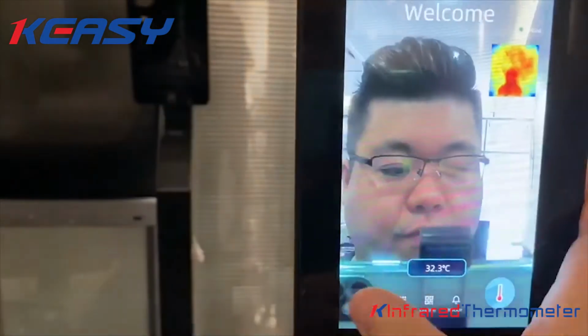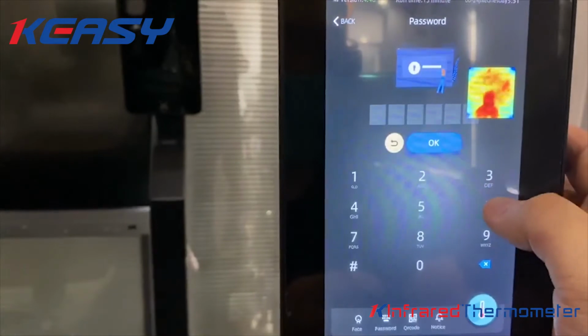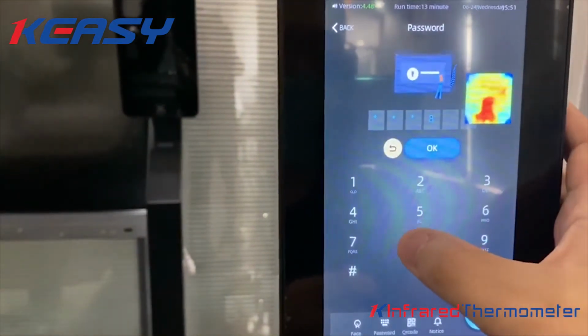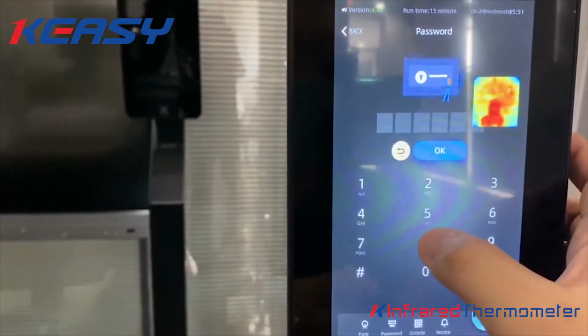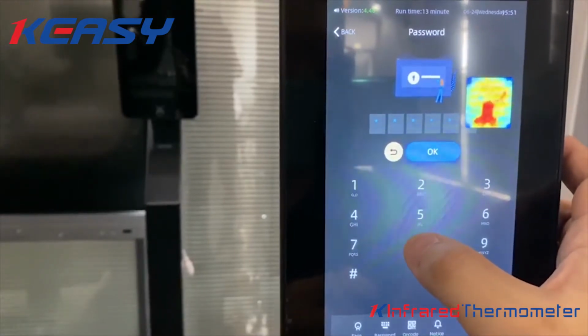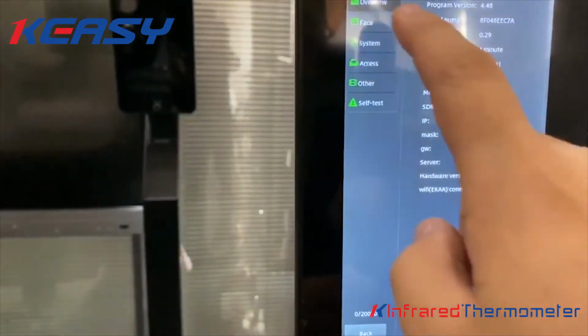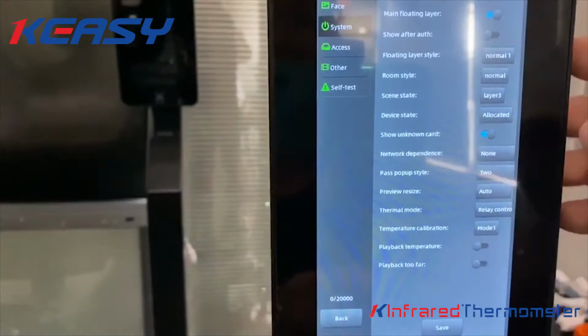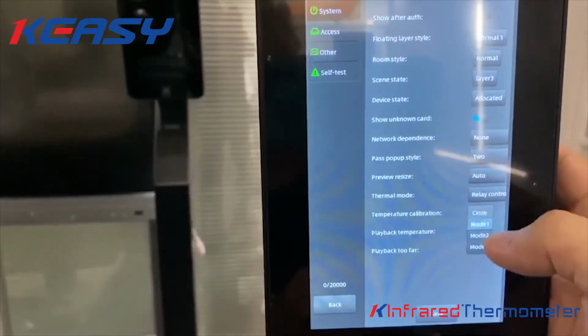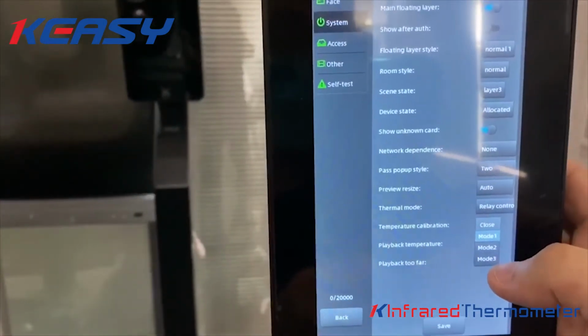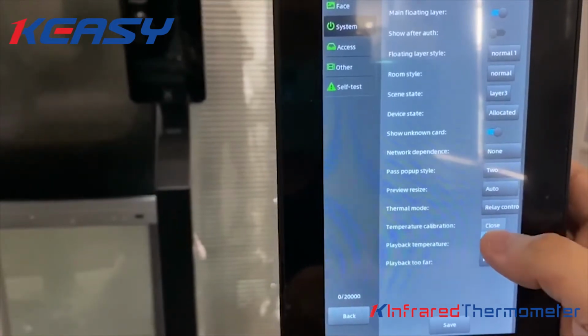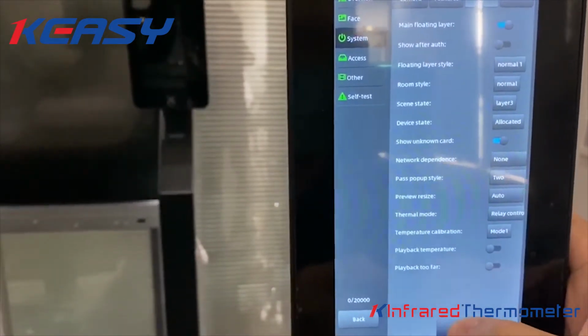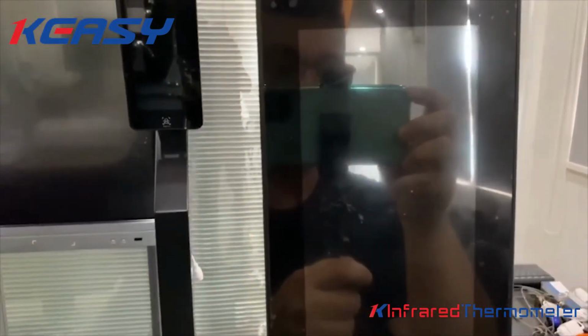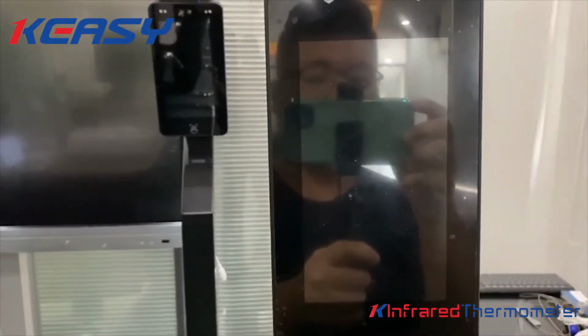So now we have to go to the device. 666, 888, 68. Okay, first we have to go to the system and set the temperature calibration from mode 3 to mode 1 and save. So after the device powers on, we will do the calibration.